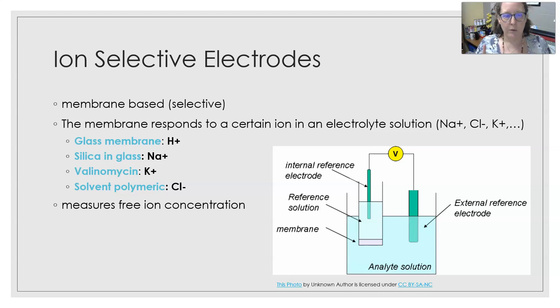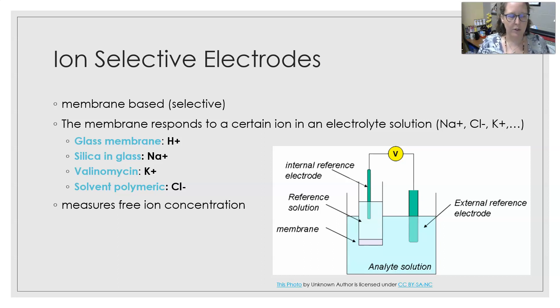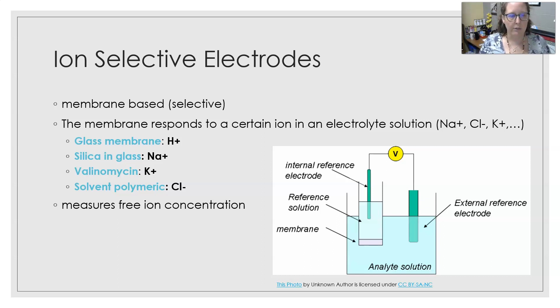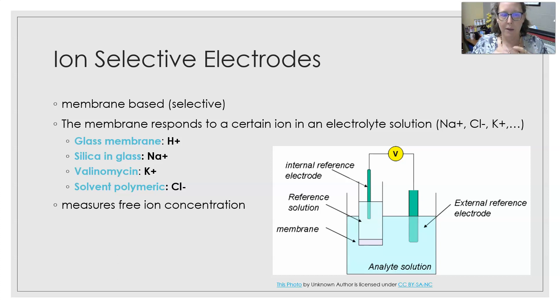A glass membrane that responds to hydrogen ion makes it a pH electrode. The silica in glass is the makeup of the sodium membrane in the sodium electrode. Valinomycin is the makeup of the membrane that measures potassium. The membrane that measures chloride is a solvent polymeric membrane. Each of these ion selective electrodes are separate and will each measure free ion concentration in the sample.